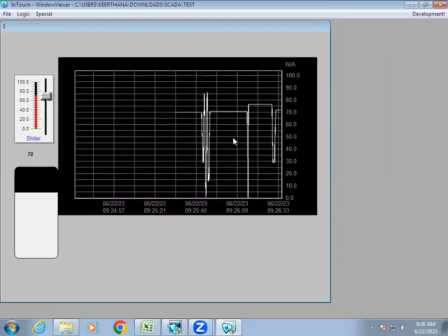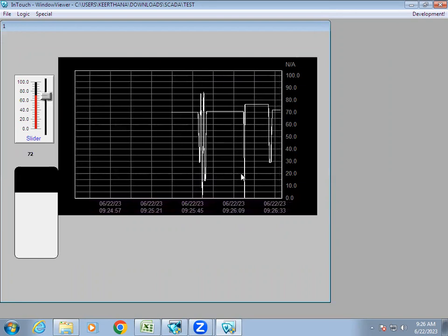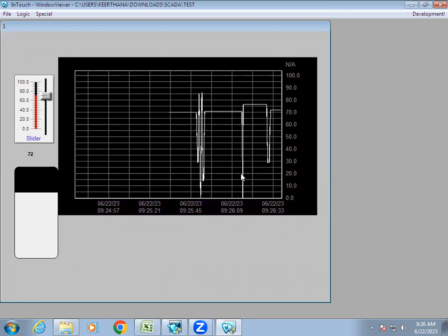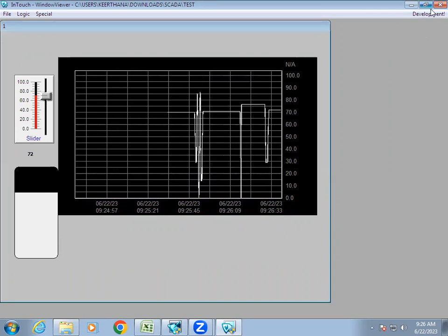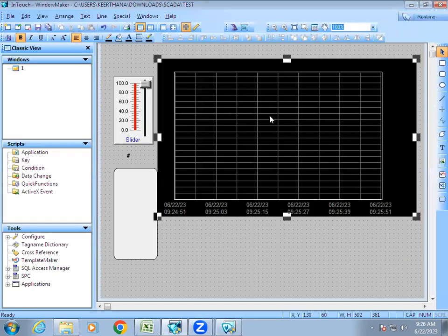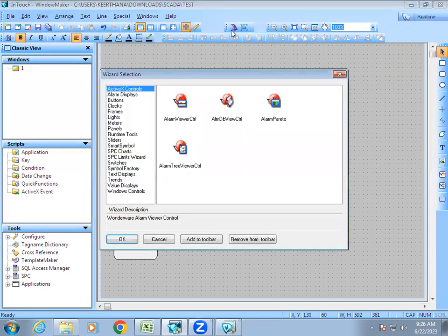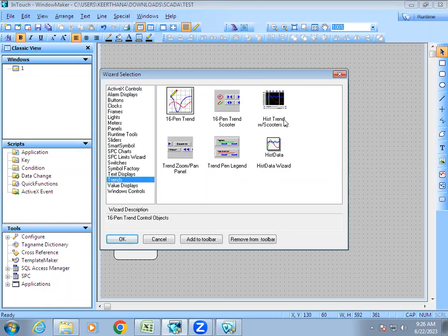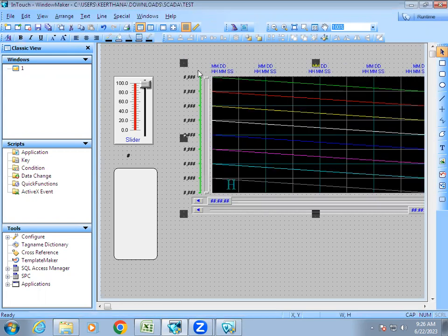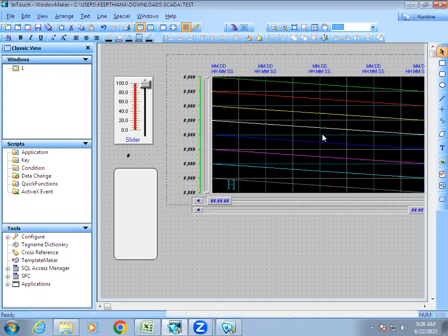If you want to see past data — maybe check it sometime later — that is not possible in real-time trend. For that we have another chart called historical trend. In the wizard, under trend, we have historical trend. Select it and place it on the screen.